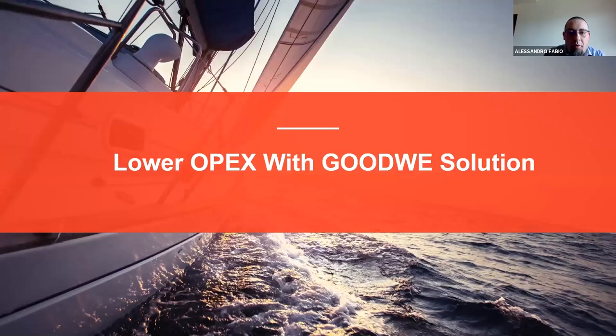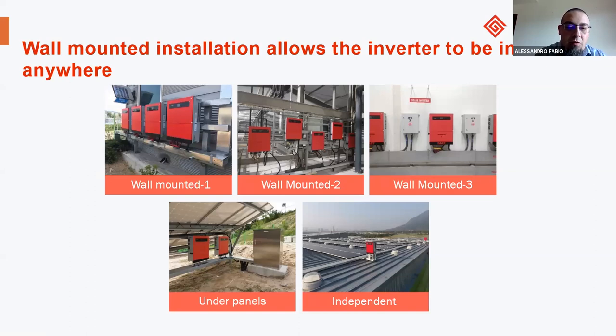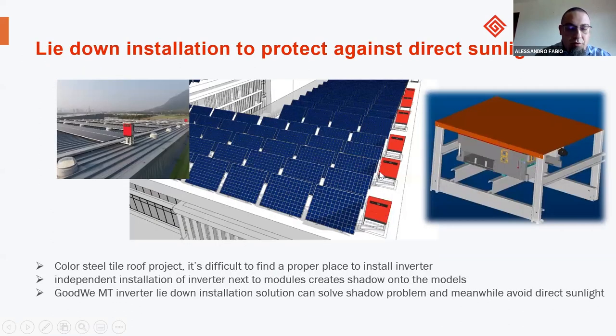So we'll also speak about the lower OPEX with GoodWe solutions. We have a lot of mounting possibilities, as you can see in the image. We have wall mounting, two or three typologies of them. And for example, under the panels or on the utility case, or independent, also on rooftops. We also use these typologies directly on the PV field, mounting on the side of the PV fields, and in some cases we also have the possibility to mount on the opposite side. If needed, it's not the optimal one, but it's also one of the possibilities.